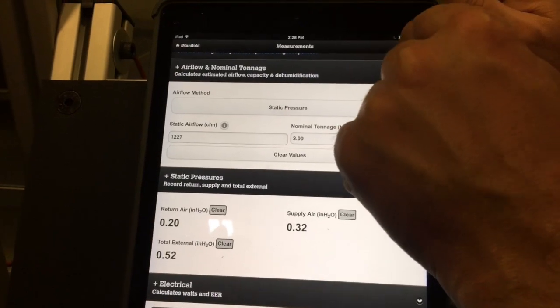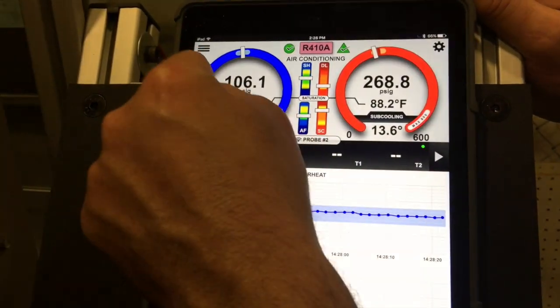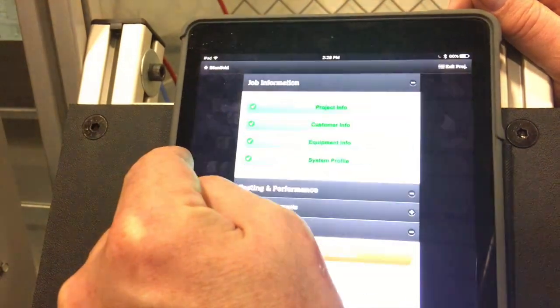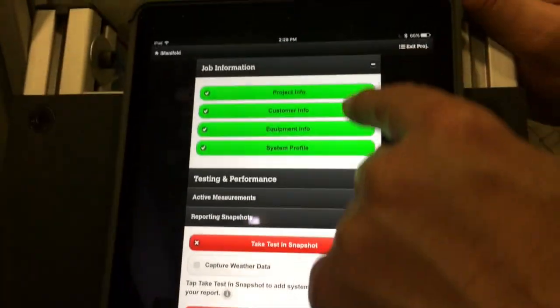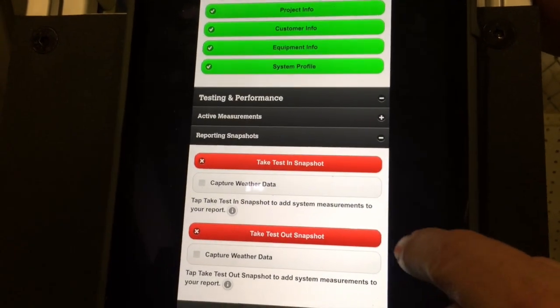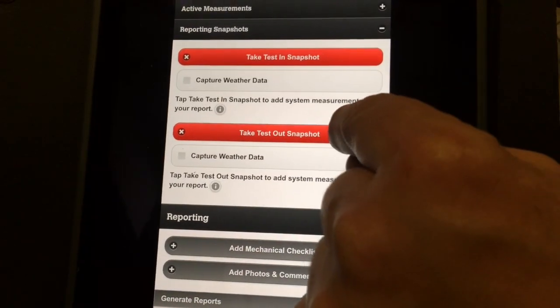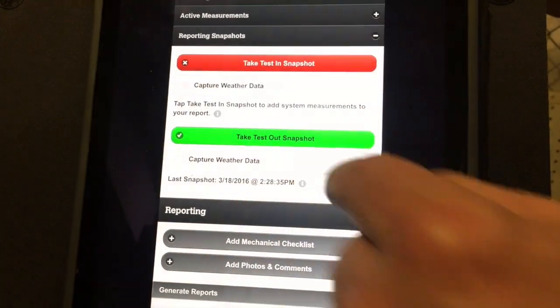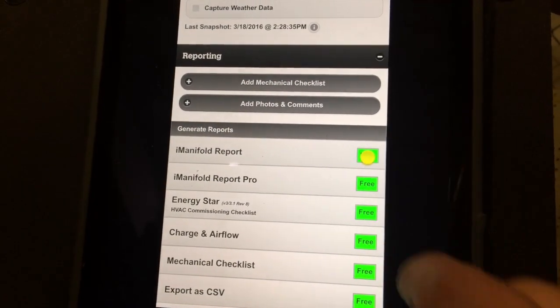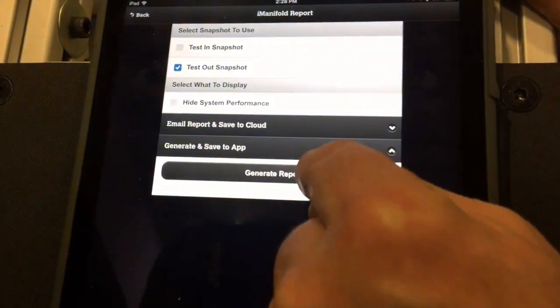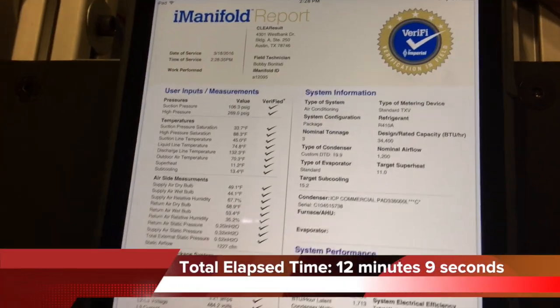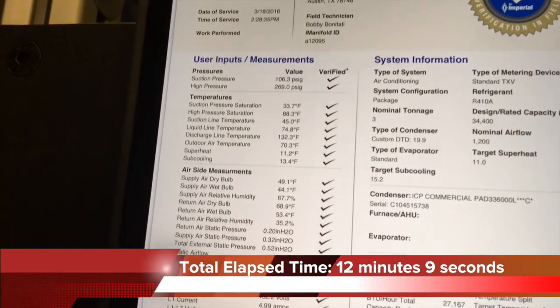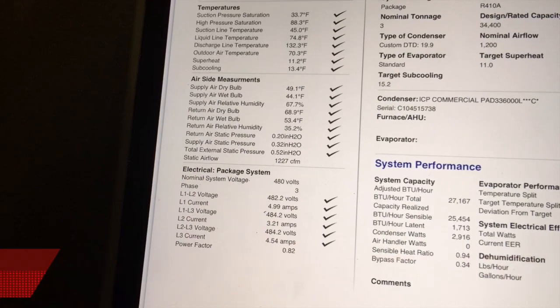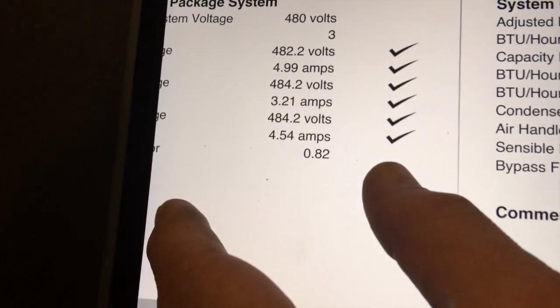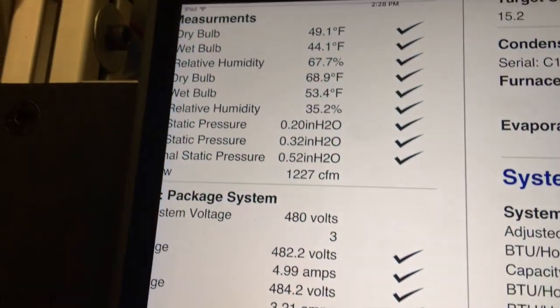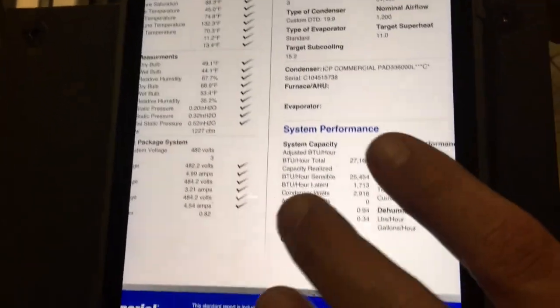So I'm going to go ahead and hit submit on the top here, and then go over here to reporting. You can see I already have my customer information filled out, so this is data that we can pull in from our cloud. So I'm just going to take a test snapshot, hit OK, go down here to the iManifold report, and we'll just generate that report. And you can see that quickly we have all the information filled out. Pressures, temperatures, air side measurements, static pressures, electrical measurements, supply, return static, all of our system performance, and everything filled out.